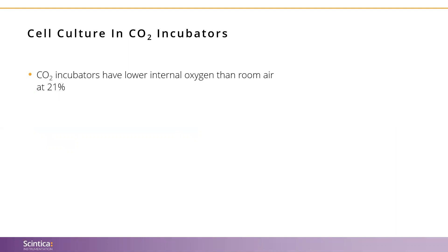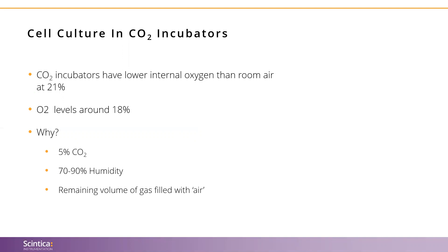So what do we know about oxygen conditions within cell incubators? I mention this because I've seen this mistake in several publications: CO2 incubators are not at 21% oxygen. They are much closer to 18%, as the partial pressure of CO2 at 5% and humidity between 70% and 90% mean there's actually less room for oxygen within these systems. Let's keep that 18% oxygen level within CO2 incubators in mind as we look at a few relevant definitions.